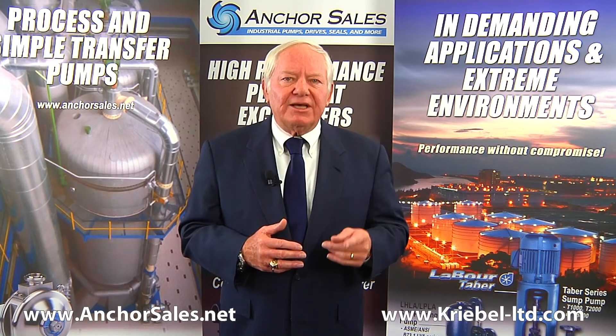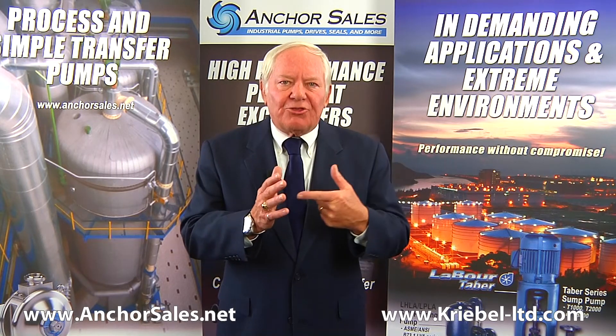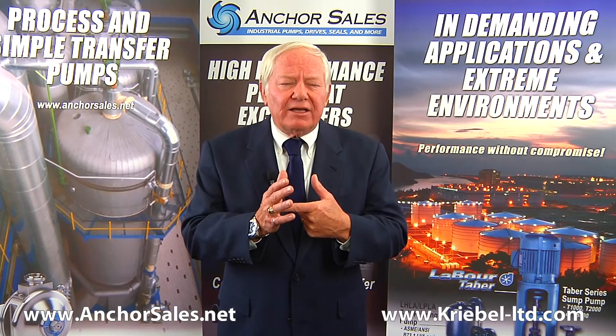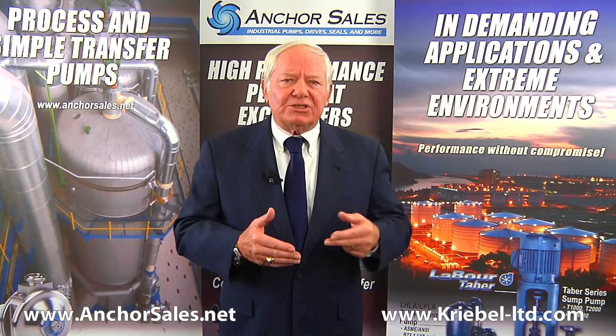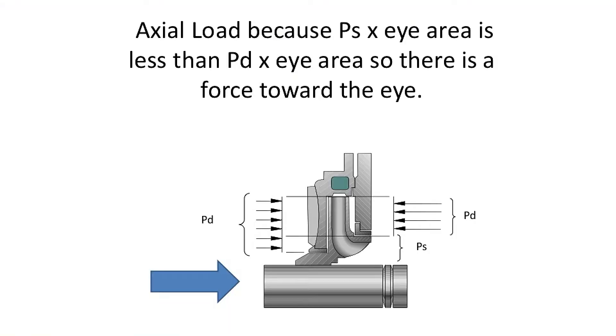All centrifugal pumps have two sets of hydraulic loads: an axial load causing a thrust toward the impeller eye, and a radial load causing a thrust perpendicular to the shaft. This illustrates how the higher pressure acting behind the impeller eye section causes an axial load toward the suction of the pump. This load must be handled by the thrust bearings. As the pump moves back on its curve, the pressure and load can increase to a point causing thrust bearing failure.